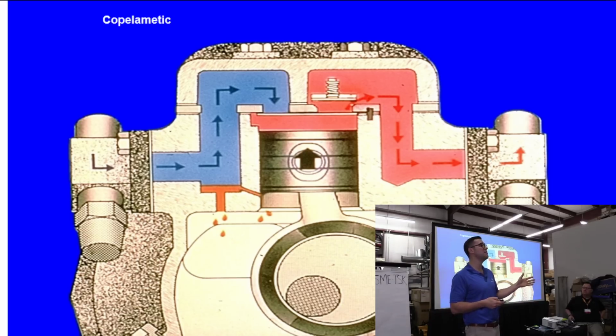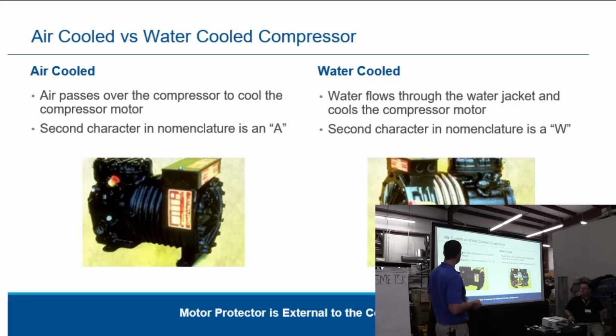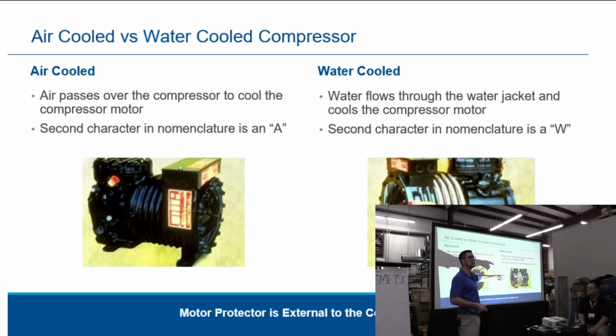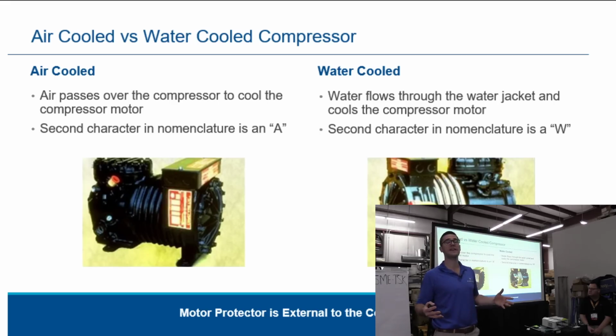If it's on the end bell or the shell, what's that type of cooling? Refrigerant cooled. Okay, excellent. Air-cooled compressor: air must pass over the body. So you have that condensing fan blowing air over the body, cooling it down. Because if you don't have that cooling, that compressor is going to start running hot and then overheat. So then there's water-cooled compressors. All it is is a copper coil wrapped around it, and you're using water to cool that compressor.